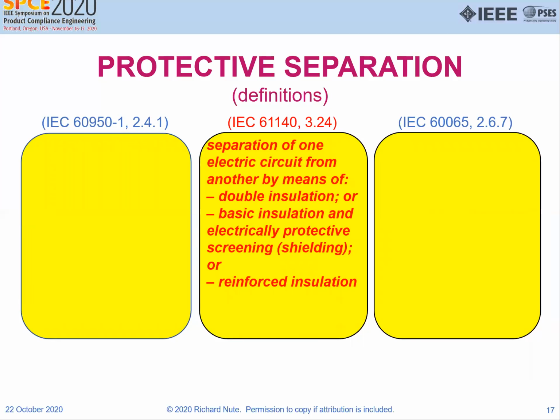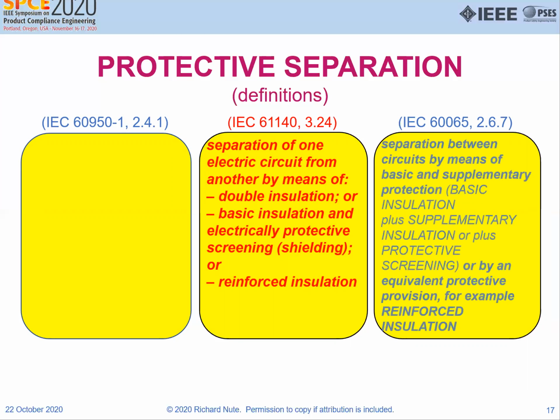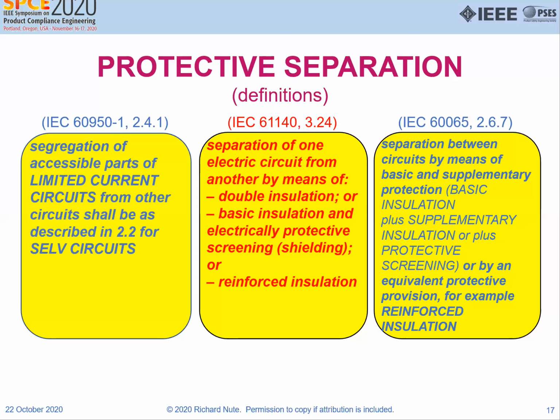And we have to look at protective separation from hazardous live, low voltage and low current, and separation of one electric circuit from another by means of double insulation, basic insulation, grounding, or reinforced insulation, classic kinds of stuff. And if we look at 65, it says essentially the same thing, separation between circuits by means of basic and supplementary protection. And finally, we also have 950, which uses a different word, talks about segregation of accessible parts of limited current circuits from other circuits, shall be as described for SELV circuits. So a SELV circuit and a limited current circuit are segregated from other circuits. Doesn't say what other circuits are.